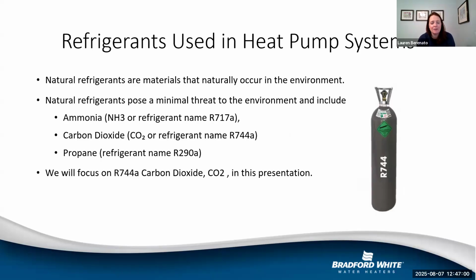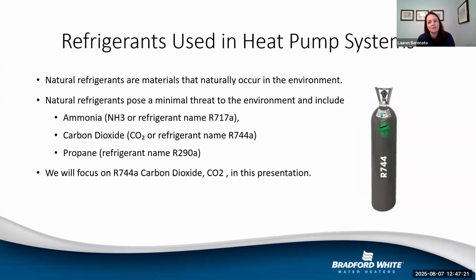You will also see R744, which is your CO2 or carbon dioxide. You'll see that for your high efficiency commercial systems. It has a very low global warming potential, which is popular. However, it operates at a higher pressure, which requires a special design. We also have your R410A, which is used in some residential as well as commercial HVAC style systems. Pros are that it's efficient and widely available. Cons are that it does have that greater global warming potential. So it is being phased down under certain regulations.